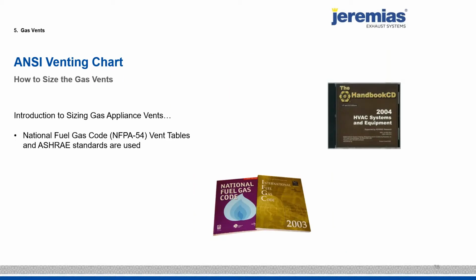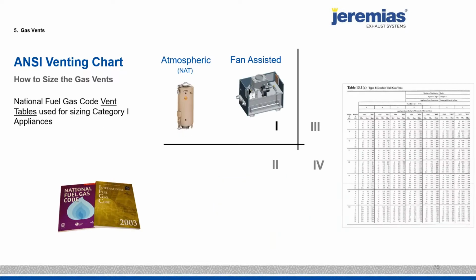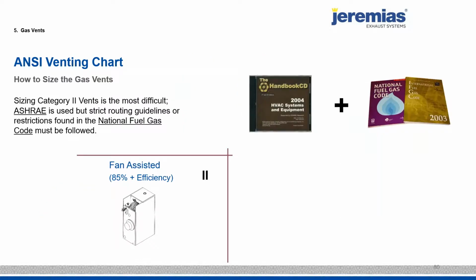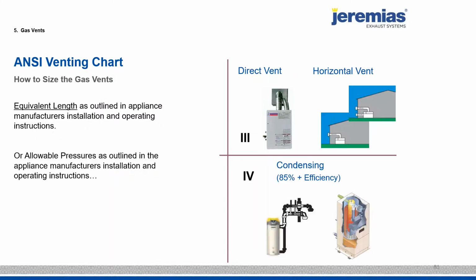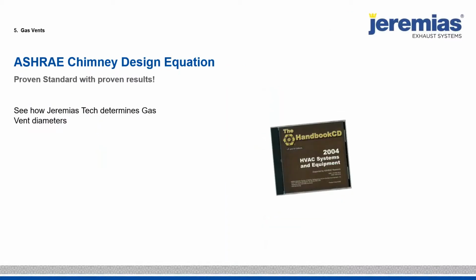A little bit about sizing these systems. We use the ASHRAE, we use the National Fuel Gas Code to size category 1. These are the venting tables. It's also good that we know about these venting tables because they have a lot of rules. So actually our tech team goes through these venting tables a lot to learn about all the rules. Sizing category 2, this is a combination of ASHRAE and the venting tables to understand the rules. And then on categories 3 and 4, how we size the gas vents, it's basically equivalent length or allowable pressures. Allowable pressures is becoming more and more popular because everyone has access to the electronic or computer chimney design equation.